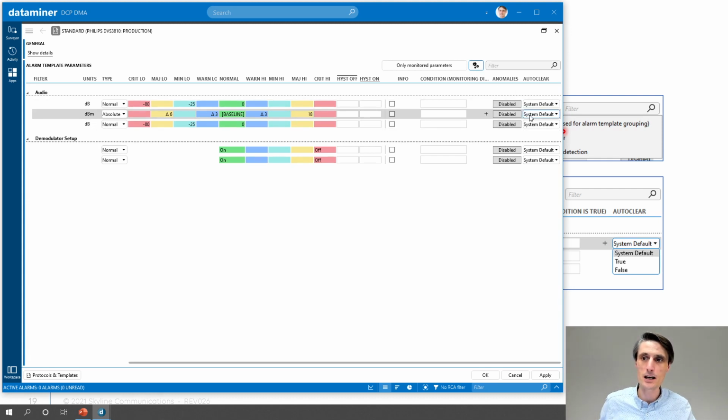But what you can also do in the DataMiner system, you can change the system default so that all the alarms that DataMiner is generating, whenever they clear, will remain in my alarm console forever as a clearable alarm, and somebody needs to go in there and right click on the alarm and say, yeah, I've seen the alarm, you can remove it now. And now it's clear and now it's gone out of my window. Okay, you can do it system-wide for all the parameters or none, but maybe I want something in between, and that's what you can do here.